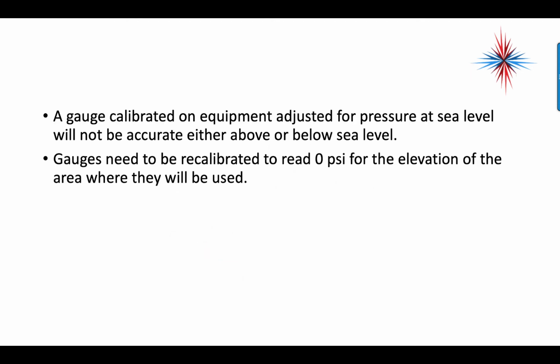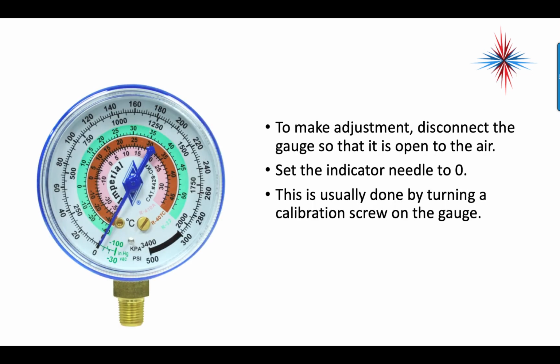A gauge calibrated on equipment adjusted for pressure at sea level will not be accurate high above sea level or below sea level. Gauges need to be recalibrated to read 0 psi for the elevation of the area they will be used. To make adjustments, disconnect the gauge so it's open to air. Set the needle to 0. This is usually done by turning a calibration screw on the gauge, and you take the cover off and there's a calibration screw right there you can turn with a small screwdriver.